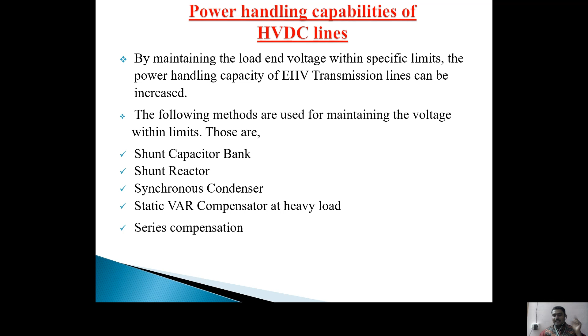Shunt capacitor banks are operated to inject reactive power for maintaining the voltage within limits at heavy loads. These are installed near the load terminals, that is factory substations and switching substations. The shunt capacitors are located near load points and in receiving substations to supply reactive power to inductive loads and to improve the power factor.